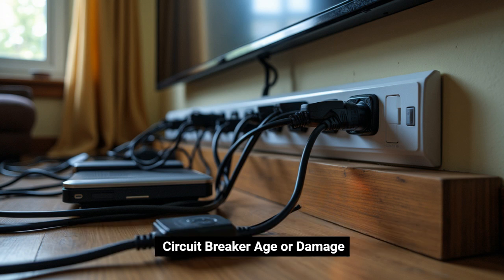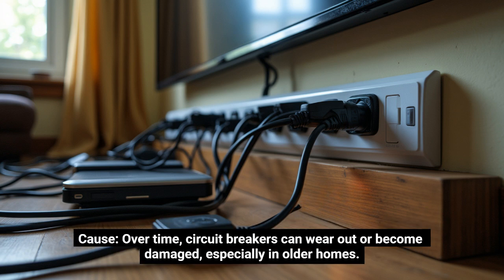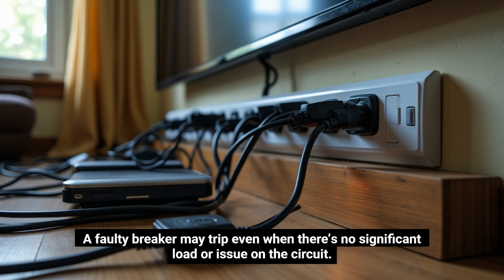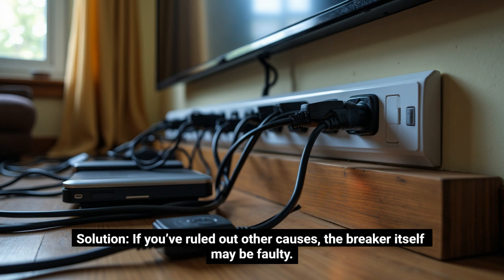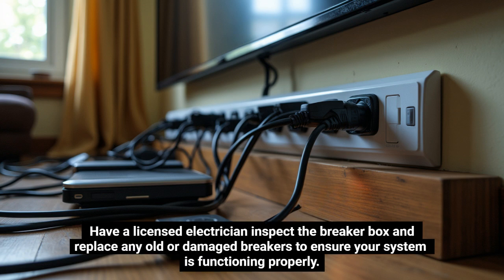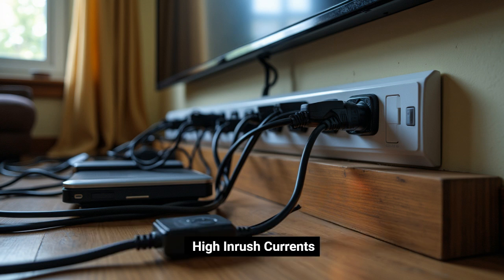Circuit breaker age or damage. Cause: over time, circuit breakers can wear out or become damaged, especially in older homes. A faulty breaker may trip even when there's no significant load or issue on the circuit. Solution: if you've ruled out other causes, the breaker itself may be faulty. Have a licensed electrician inspect the breaker box and replace any old or damaged breakers to ensure your system is functioning properly. High inrush currents.